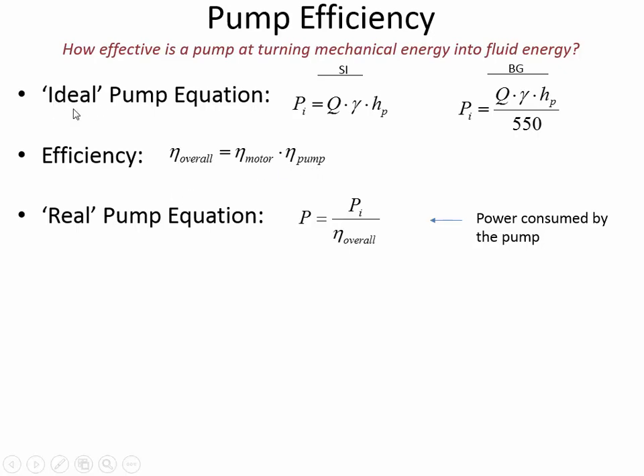So compare the ideal pump equation to what I'm calling here the real pump equation. In real world application, you'll have some efficiency that's maybe, if you're lucky, around 60% when you consider both the pump and the motor. And so ideally, maybe you needed 1,000 watts to move the water at some flow rate and with some pump head. But you'll notice since you're dividing by a fraction that's less than 1, your actual power is going to be larger.